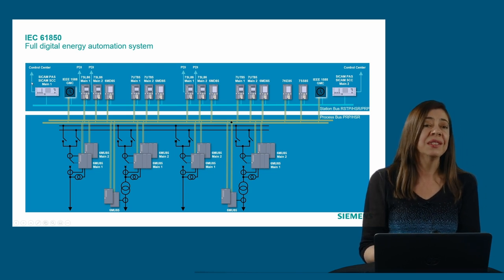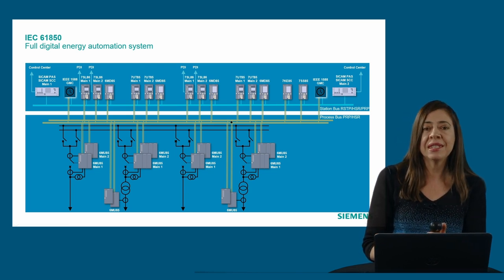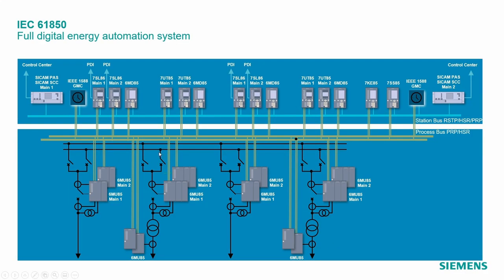So how can we get this redundancy, complete redundancy in the system? So basically, we will be having redundant merging units. For process bus stations, we don't need to have 3, 4, or 5 different cores in the instrument transformers. It is enough having 2 and feeding one to merging unit 1 and the second one to merging unit 2, sending these 2 signals to the process bus network, where all the protection devices can access both types of information and select the one that they need for the protection algorithm.